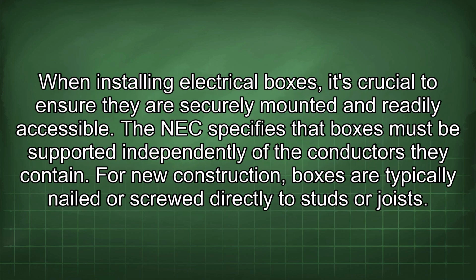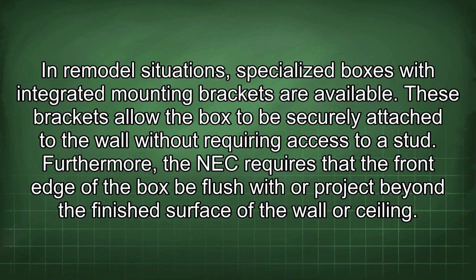When installing electrical boxes, it's crucial to ensure they are securely mounted and readily accessible. The NEC specifies that boxes must be supported independently of the conductors they contain. For new construction, boxes are typically nailed or screwed directly to studs or joists. In remodel situations, specialized boxes with integrated mounting brackets are available. These brackets allow the box to be securely attached to the wall without requiring access to a stud.